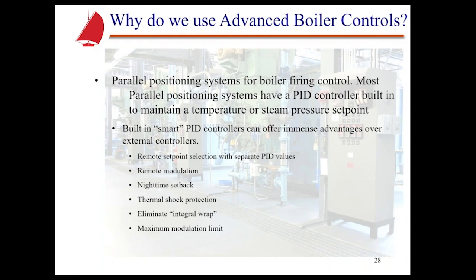Also, eliminating integral windup is important. If we're actually sitting there with a PID, it can actually end up with integral windup. In other words, overshoot the set point big time once we've gone into modulation. So this can be built into the control also.